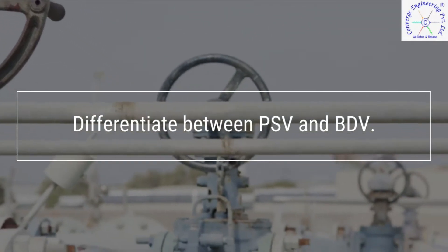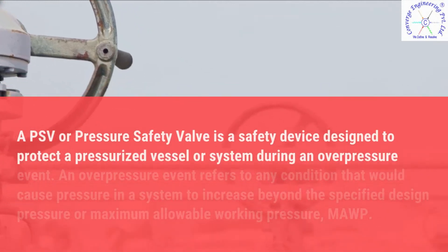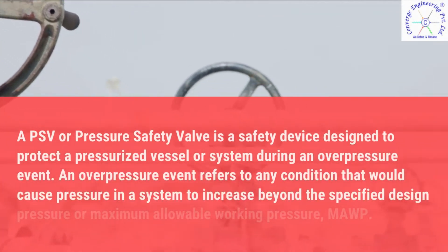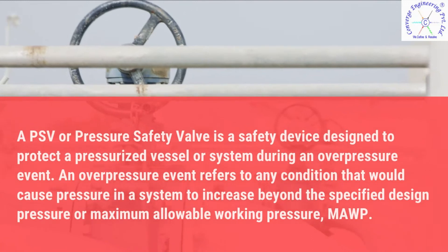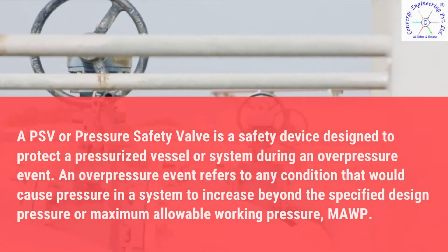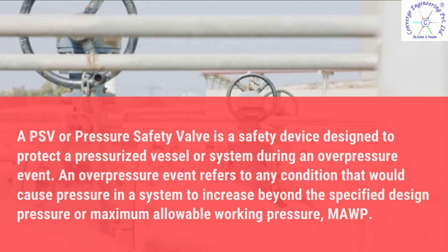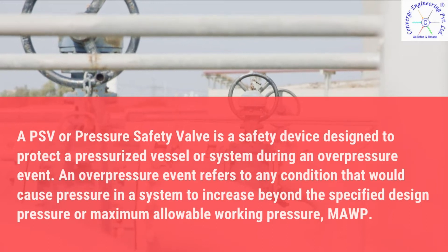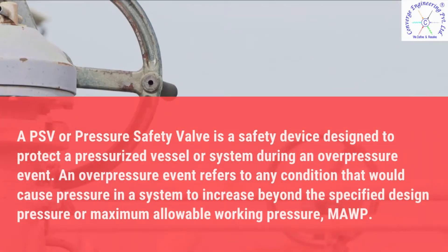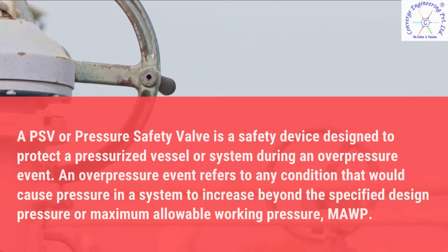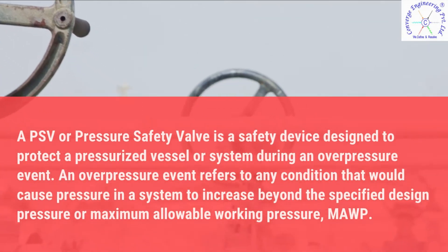Differentiate between PSV and BDV. A PSV, a pressure safety valve, is a safety device designed to protect a pressurized vessel or system during an overpressure event. An overpressure event refers to any condition that would cause pressure in a system to increase beyond the specified design pressure or maximum allowable working pressure, MAWP.